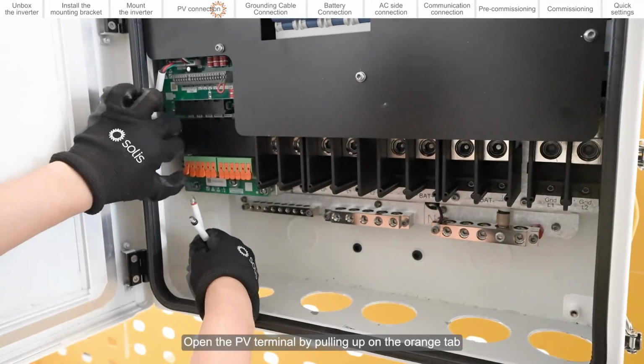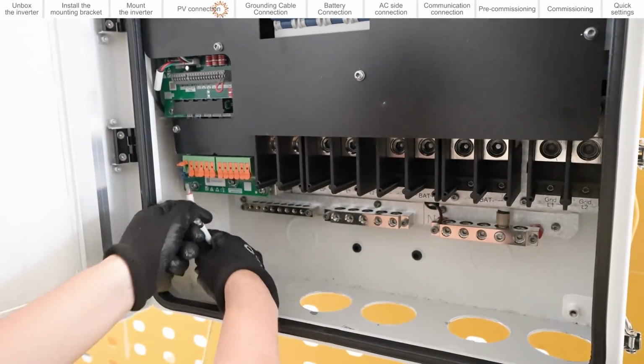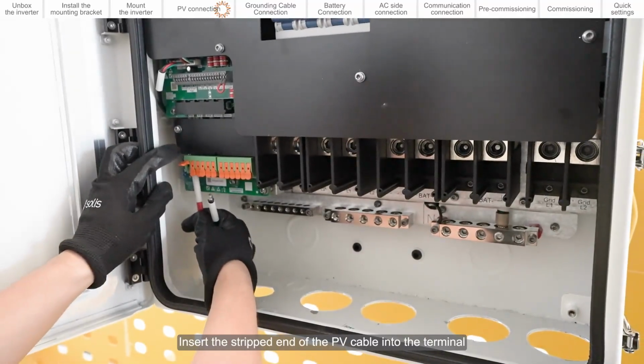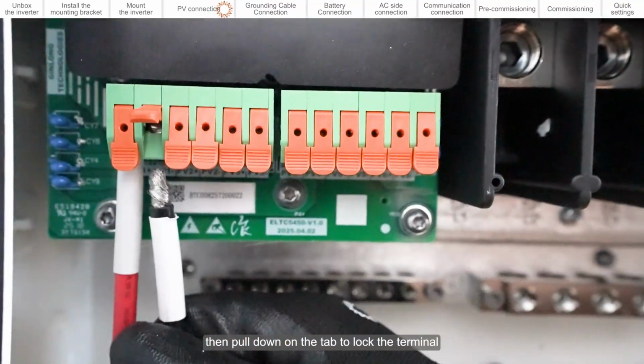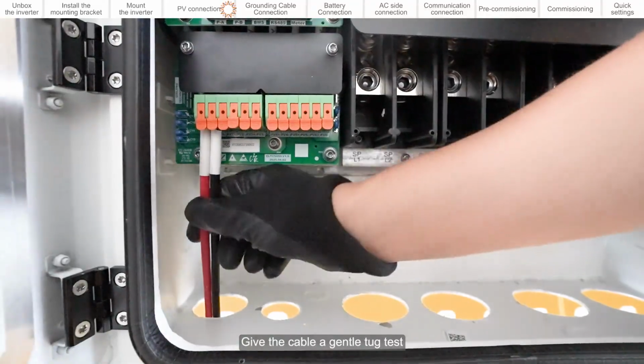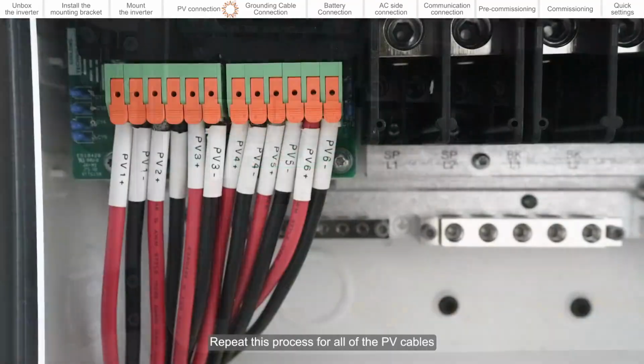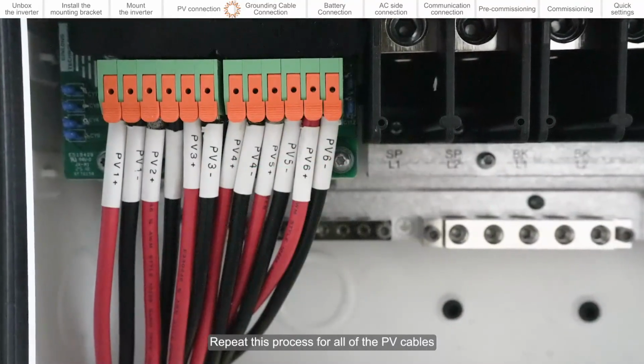Open the PV terminal by pulling up on the orange tab. Insert the stripped end of the PV cable into the terminal, then pull down on the tab to lock the terminal. Give the cable a gentle tug test. Repeat this process for all of the PV cables.